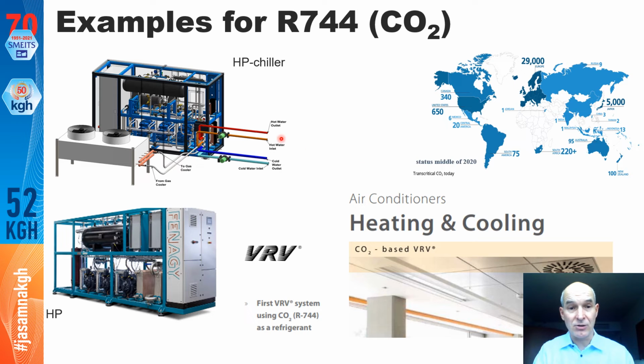On the left hand side, I show you a heat pump chiller, which utilizes the benefit of producing hot water at high temperature lift for the heat pump, but also producing chilled water at the same time. This can be very energy efficient if you utilize both the hot and cold side at the same time, which is quite interesting, for example, for a hotel where you need a lot of hot water, which you can store, and you need chilling of the equipment, rooms or kitchen or whatever.